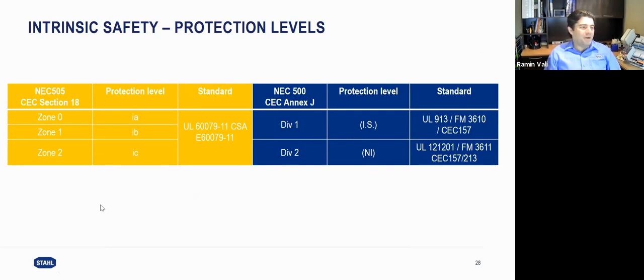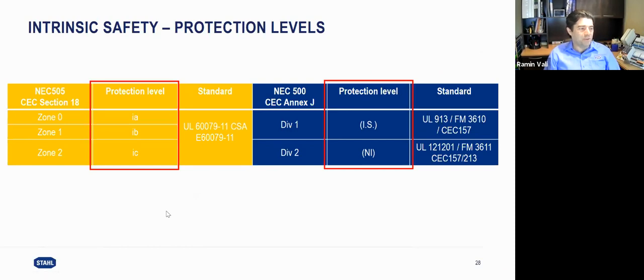Let's look at the summary of our standard for the intrinsically safe. What we can see on the left is based on the NEC 505 or CEC section 18, talking about the zones. EXIA field devices are recognized and accepted to be installed in zone 0. That means an installation in zone 0 can tolerate 2 levels of fault. EXIB field devices can be installed in zone 1, which means 1 fault can be tolerated, and EXIC field devices can be installed in zone 2.